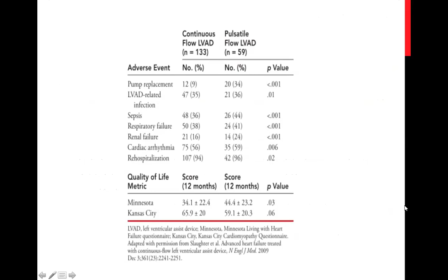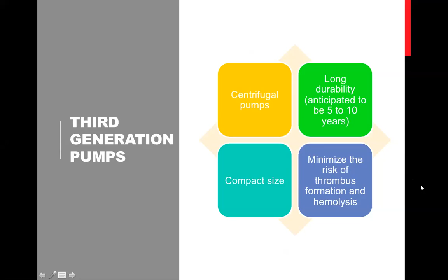Okay, third generation centrifugal pumps, where long durability is anticipated to be 5 to 10 years. Compact, smaller sizes minimize the risk of thrombus formation and hemolysis with the pump. So the HeartMate 3, the famous one, is a fully levitated centrifugal flow device, commercially available in Europe, the United States, and here in the region. The rotor spins at rates of 3,000 to 9,000 RPM and generates up to 10 liters per minute of blood flow. It incorporates rapid changes in rotor speed to create an intrinsic artificial pump pulse.